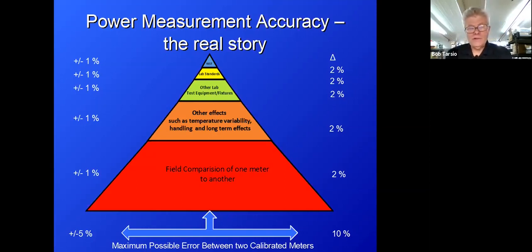What it all boils down to is that you can send a meter to them. Let's say, for example, we could send one of our meters off to NIST. I've never done it, by the way, because of the expense of it, and I'll tell you about that in a second. You can send it, and they'll measure it, and they'll say, this is what the percent of error is from the standard. However, the percentage of error from the absolute standard to what they're measuring your device to be will be within plus or minus 1%. So what that means is they can't tell you any better than about plus or minus 1% how close it is to their standard. That's pretty good, by the way. You've got 99% that you know is accurate, and 1% is the error. Well, that's a primary standard.